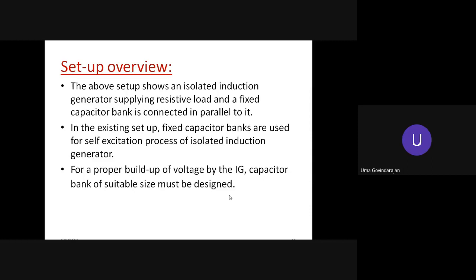So initially in the existing setup, fixed capacitor banks are used for the self-excitation process. I'll repeat this self-excitation process once again. Due to the residual magnetism present in the machine, the residual voltage will be available, and with that voltage the capacitors will get energized. When the machine starts moving slowly, when the mechanical input is given, the energy stored in the capacitor will supply a small amount of reactive power.